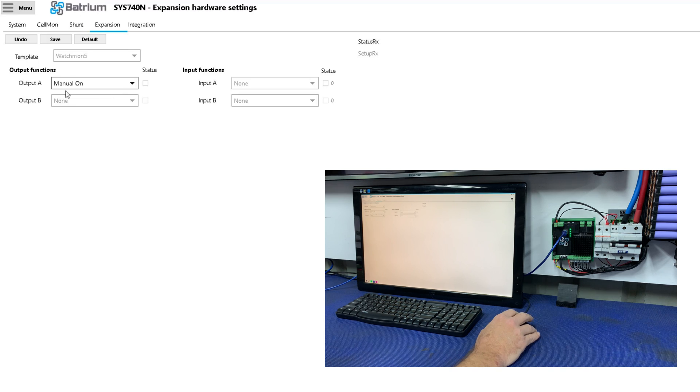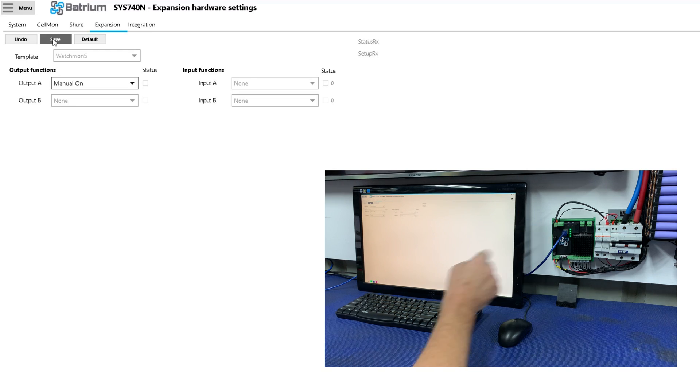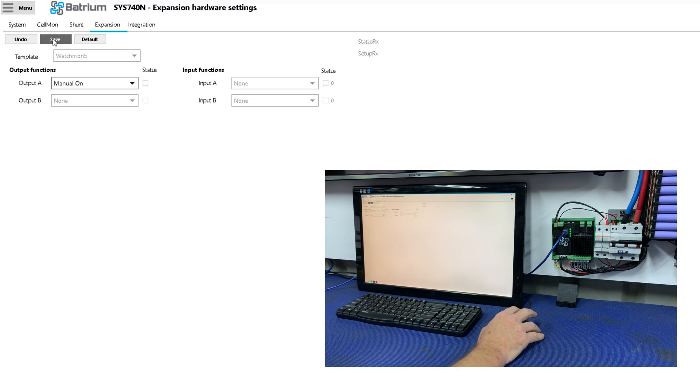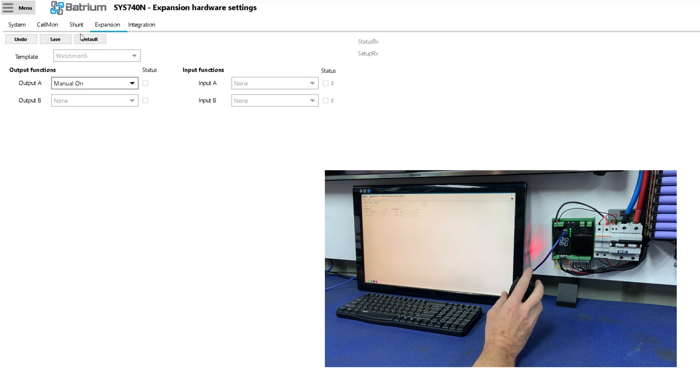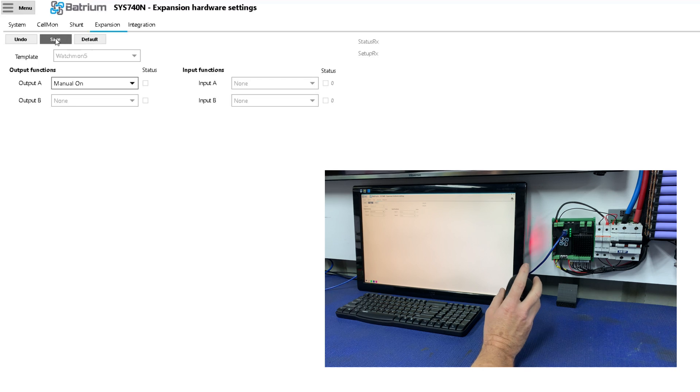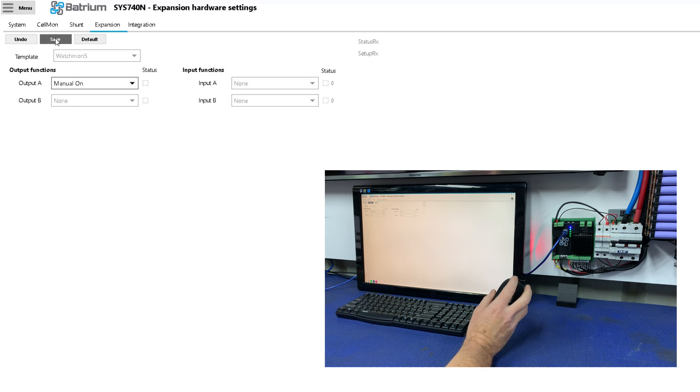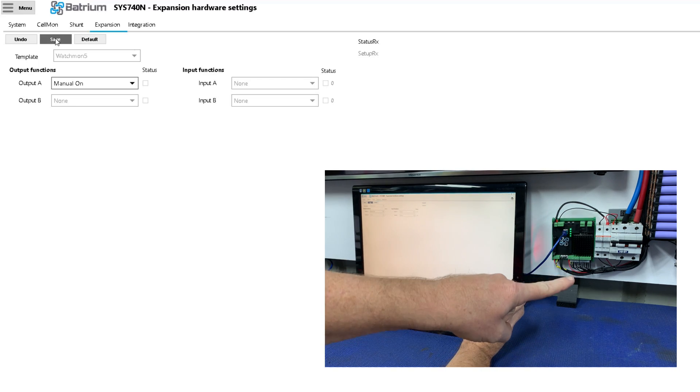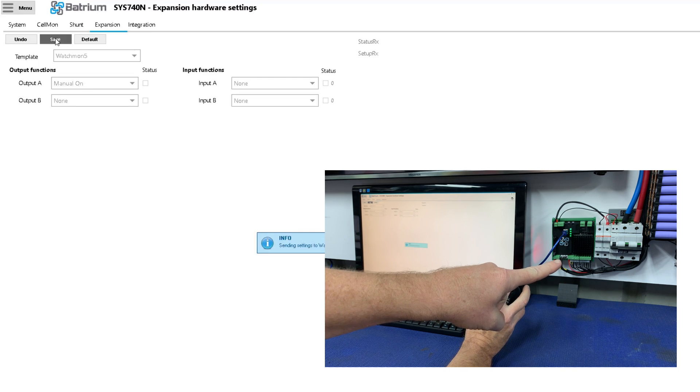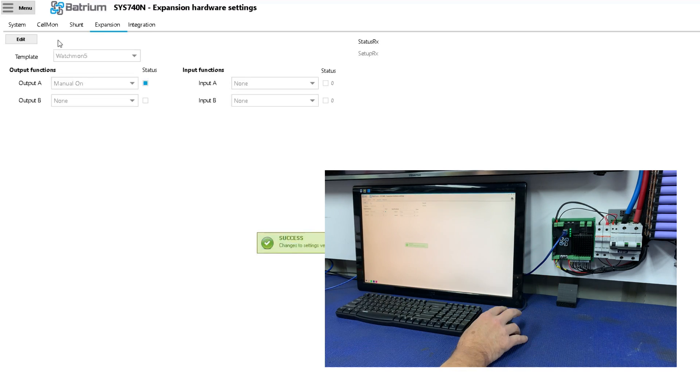Now we have got manual on selected, and we're going to hit save. Now as soon as we hit save, the trip will trip so to speak. So I'm not sure if you can actually see my finger here, but I will hit save, I'll hold it up, and then three, two, one, click, and it trips.